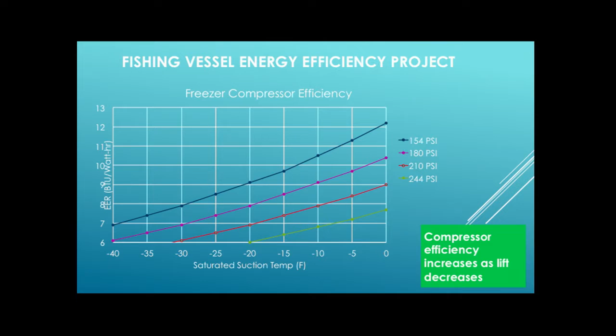The higher lines are more efficient, the lower lines are less efficient. So when you bring that discharge pressure down, you reduce that lift, you can see your energy efficiency substantially goes up. On the ship I was on, it literally went from about 6 up to about 11 or so. Significant change, just strictly by changing the operation of the valves.